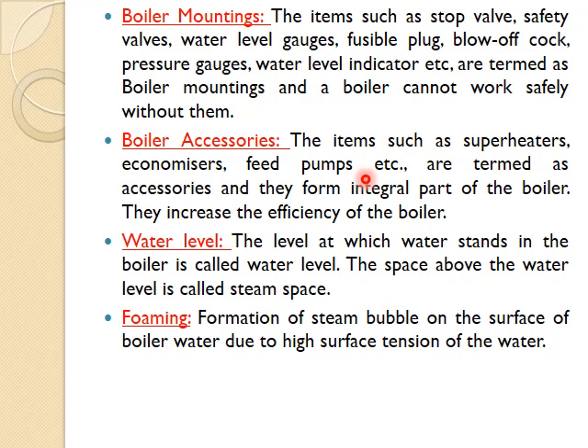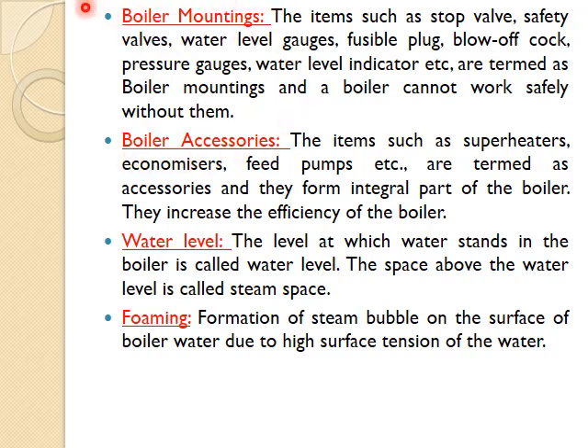Boiler accessories: items such as superheaters, economizers, feed pumps, etc. are termed as accessories. They form an integral part of the boiler and increase its efficiency. Without mountings a boiler cannot run, but without accessories we can run the boiler — however, we cannot maintain efficiency. So to boost efficiency we need accessories, and for safe operation we need mountings.